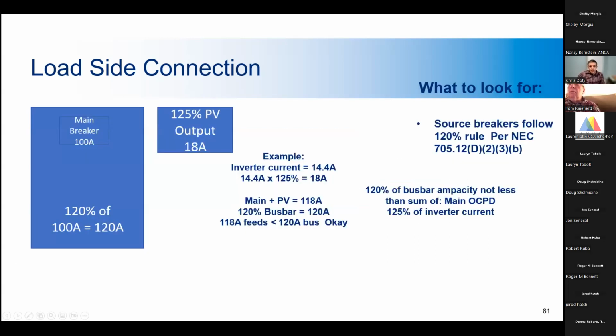All right, so here's a simple look at a load side connection calculation that's used to determine if the panelboard is large enough to accommodate the PV system. Like I said, this is known as the 120% rule. So we have the inverter current. The output of the inverter is 14.4 amps. Sizing the breaker for 125% of that, you get to 18 amps. The main breaker is 100 amps.